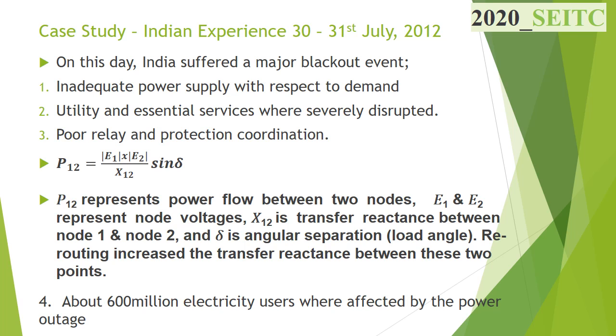The northern region was generating less than its demand, so its frequency dropped and it went into blackout due to the operation of under-frequency relays. Due to the loss of the northern region, the eastern and western regions were left with a surplus of generation, and the frequency in this region shot up. This also caused a few of the west region generating units to shut down, thereby causing the grid to be separated into two islands, the northern region and the eastern region, with one island, the eastern region, surviving and the other, the northern region, collapsing. About 600 million electricity users were affected by the power outage.